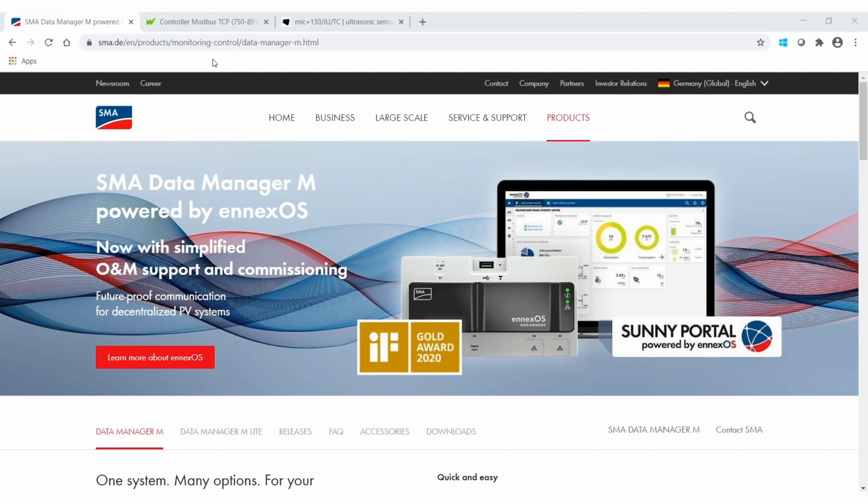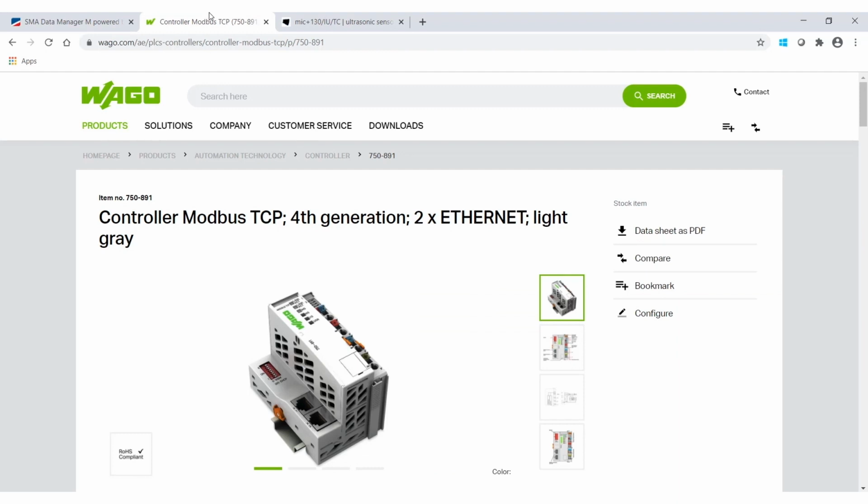With this screencast we are going to demonstrate how you can set up a diesel tank fill status sensor in the Data Manager. The components I use are a WAGO 750 I/O bundle, so this guy here, and a 4 to 20 milliamp ultrasonic sensor, this.